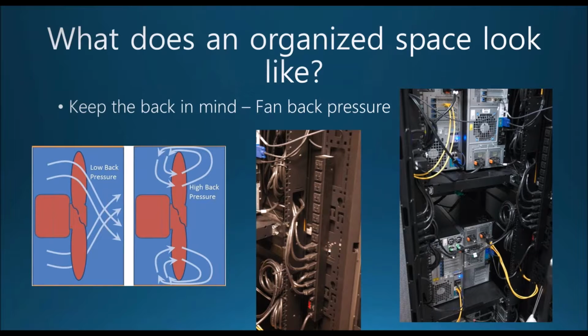In that middle picture, on the sides of the cage, I use a power distribution unit, basically a long power strip that supports a lot of power. I run that down one side, and all my servers have 2 power ports with redundant power supplies. So if a power supply goes bad, it alerts us, we unplug it, slide the old one out, slide the new one in, plug it back in, and we're all set. The great thing about dual power supplies is the server never shuts off.